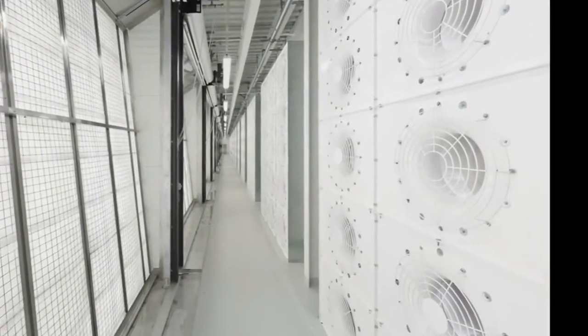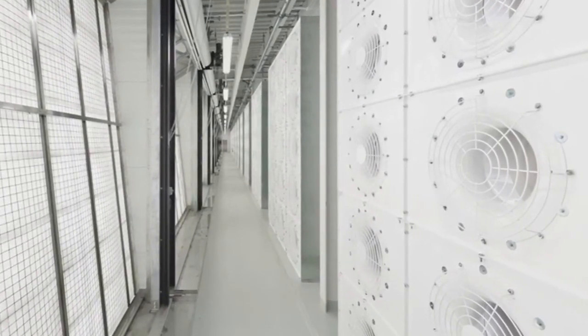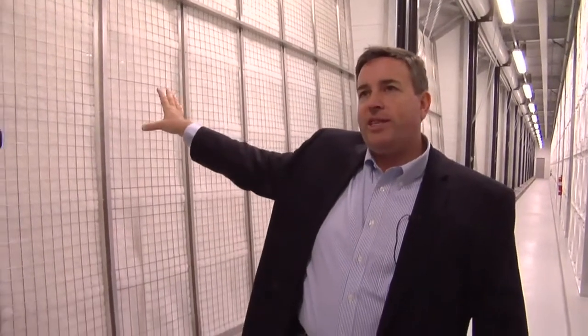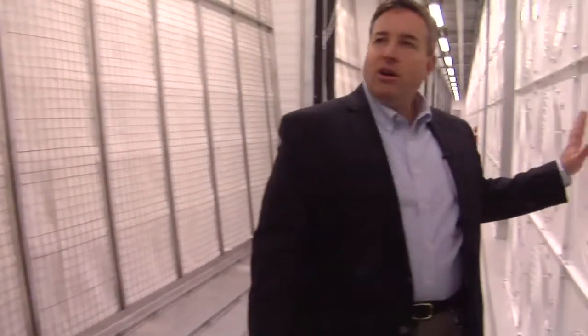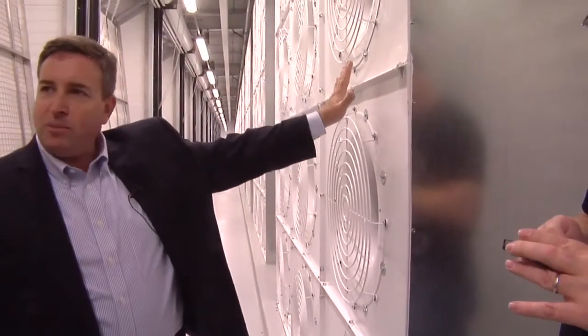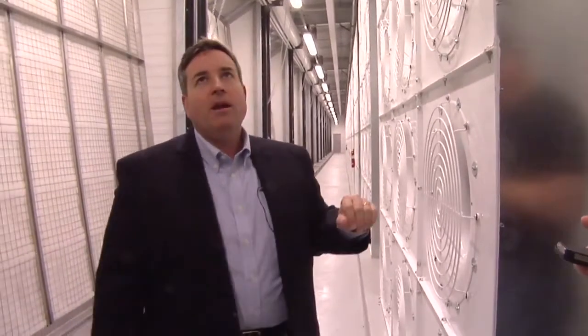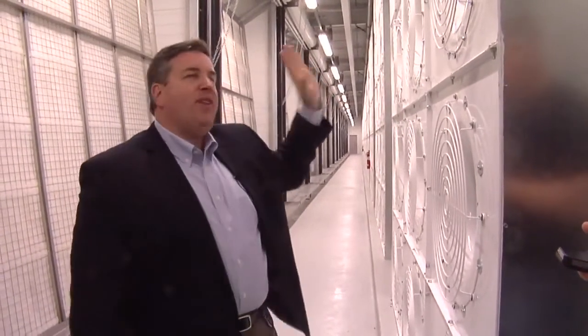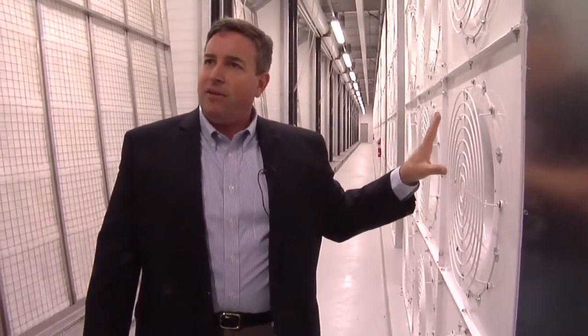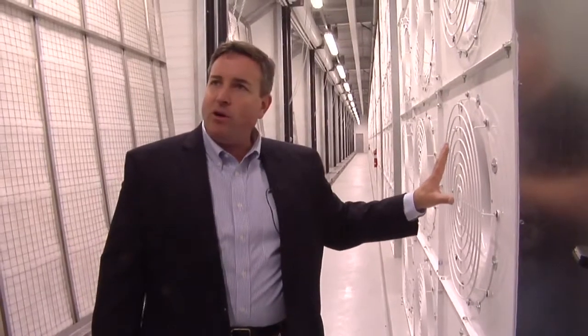So at the mist eliminator on my right side here, you can feel there's no moisture carryover, just cool, somewhat moist air. The fans here are drawing that air through the system and pushing it into the next space, which then directs it down into the space below. These, what we call fan walls, have very, very highly efficient fans in them. They have small, like 5 horsepower motors.